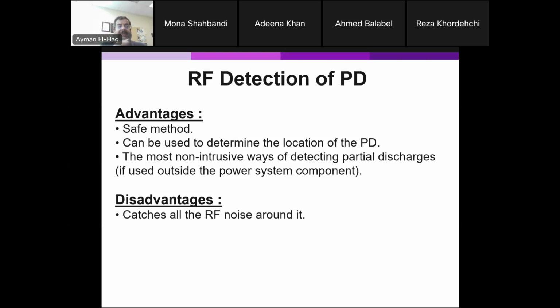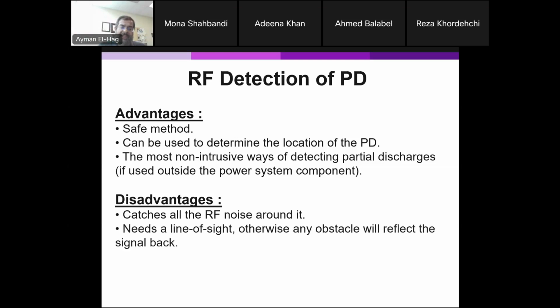Disadvantages, this is one of the major disadvantages of the RF antenna. It's an antenna, so it will detect any electromagnetic waves, which is bad because sometimes you detect something and think there is a partial discharge, but it's not. Basically, it is noise coming from a source of electromagnetic waves. So you have to have either some experience about the nature of the partial discharge, or you have to have denoising techniques to remove those noises from the measured signals.